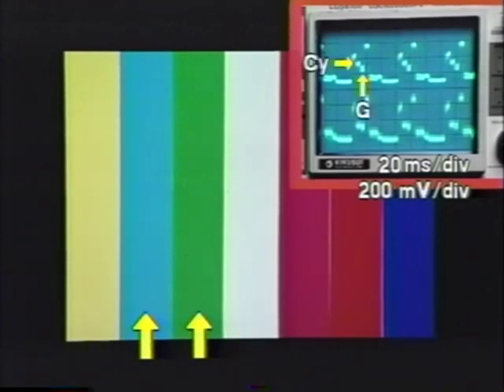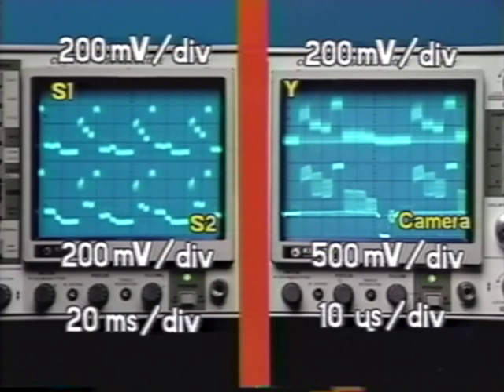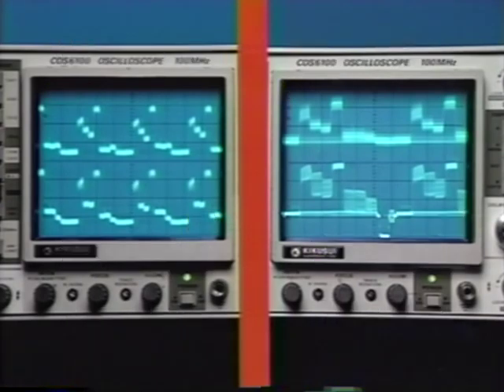We can also see that the yellow and white stripes produce the largest S1 and S2 waveform levels. The cyan and green stripes produce the medium waveform levels, and the 3 remaining colors, magenta, red, and blue, produce the smallest waveform levels. If the Y, S1, and S2 waveforms do not look like the ones shown, then the separator stage or their support signals are likely to be at fault.